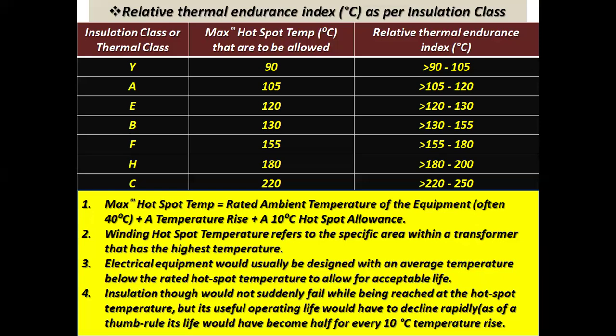Electrical equipment would usually be designed with an average temperature below the rated hotspot temperature to allow for acceptable life. Insulation, though, would not suddenly fail while reaching the hotspot temperature, but its usual operating life would have to decline rapidly. As a thumb rule, its life would become half for every 10 degrees centigrade temperature rise. Most important to note.